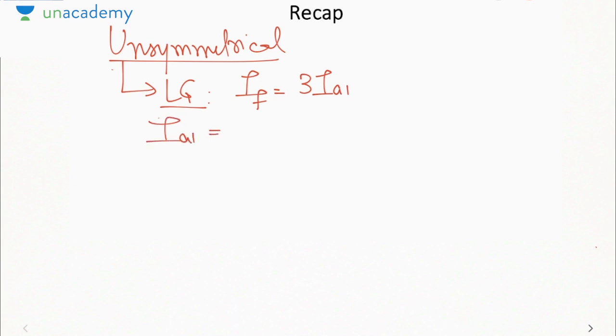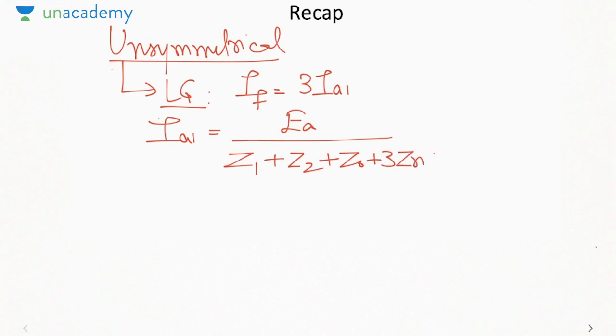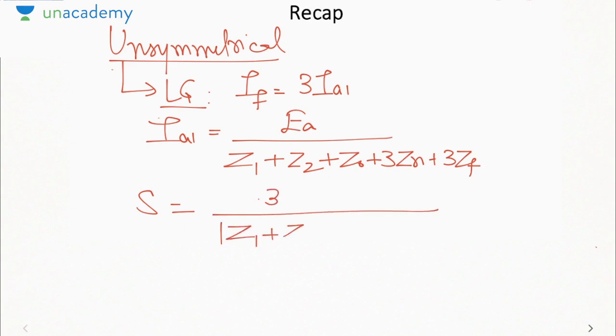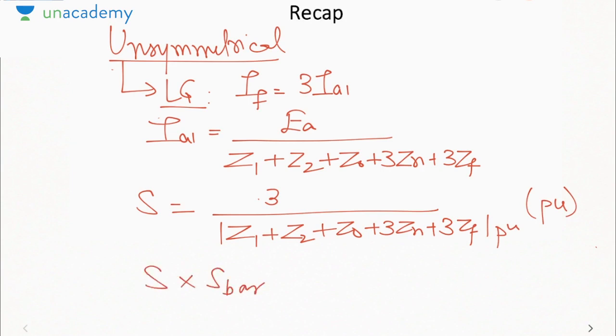where IA1 was equal to EA by Z1 plus Z2 plus Z0 plus 3Zn plus 3ZF. And the short circuit MVA was 3 by mod Z1 plus Z2 plus Z0 plus 3Zn plus 3ZF. Okay, in PU. This gives the short circuit MVA in PU. Now S into S base 3 phase will give me short circuit MVA in the units of MVA. So this was for the case of LG fault.